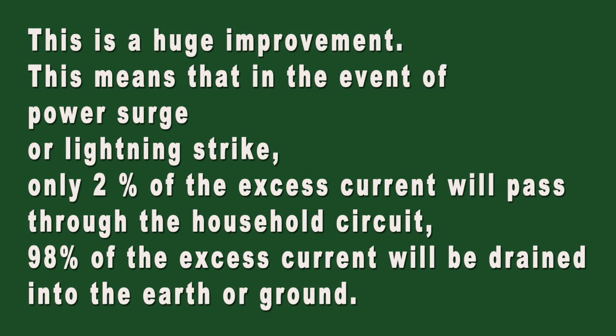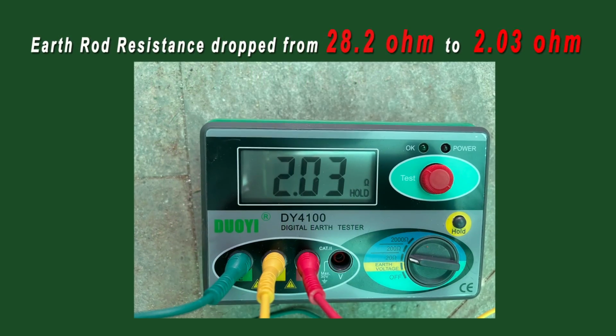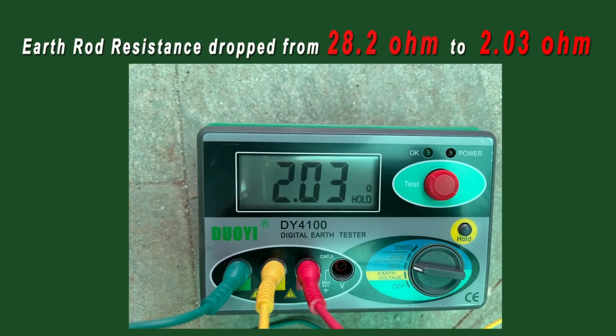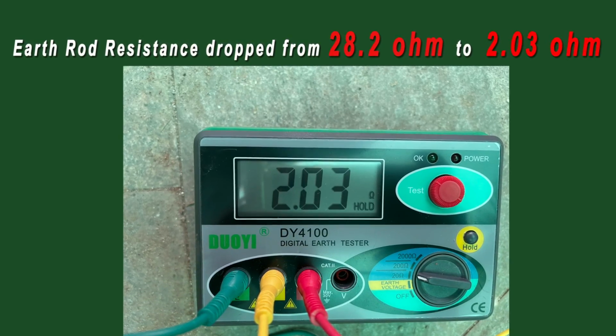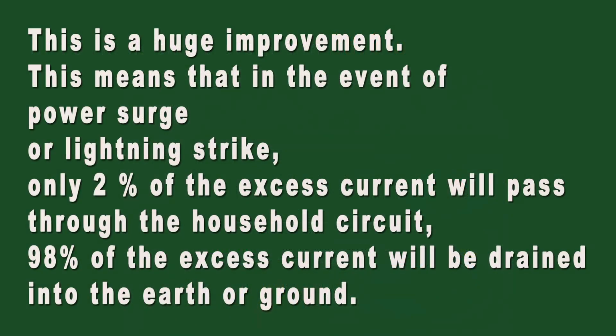When the project was completed, the ground resistance of the copper rods improved tremendously. It dropped from 28.2 ohm to now only 2.0 ohm. This is a huge improvement. This means that in the event of power surge or lightning strike, only 2% of the excess current will pass through the household circuit, 98% of the excess current will be drained into the earth or ground.